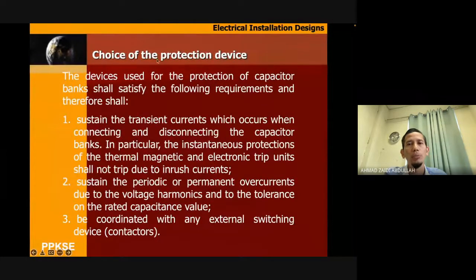So why the choice of protection device? The device used for protecting the capacitor shall satisfy the following requirements, and there are 3 reasons why we provide the protection. Number 1 is we need to sustain the transient current which occurs when connecting and disconnecting the capacitor bank. So that's why we need to install protection before the capacitor. We saw the series and parallel connection, and the last component is the capacitor. So before connection to the capacitor, we need to protect it because the capacitor is a reactive component. If we do not protect it properly, it can become a bomb.